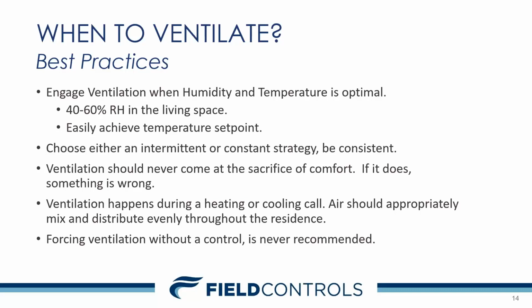An example of that would be many controls that exist on the market today. If it is too hot based upon temperature and humidity lockout, it will say, do not ventilate for this hour, stack it on the end of the 24-hour cycle. Often that happens when the temperature drops during the middle of the night, but the dew point's at the highest. So they've missed 8 hours of ventilation time during the day, and that damper or ventilator is pretty much just going to run for the remainder of that missed call at the dew point when it's highest, creating humidity issues.